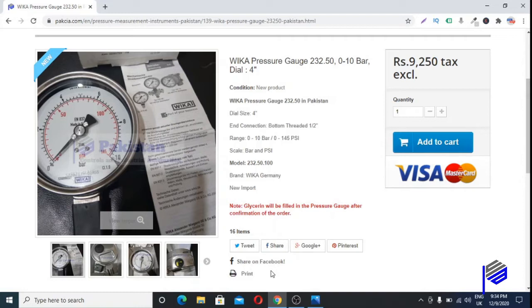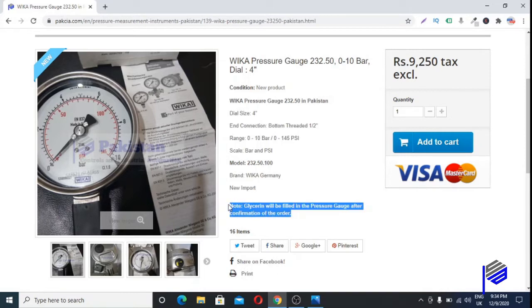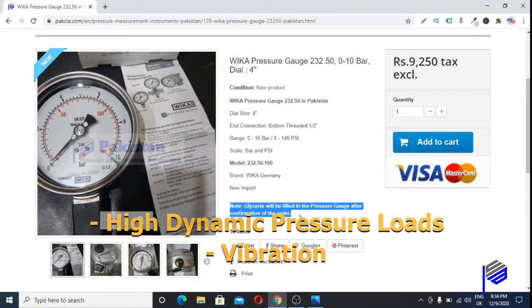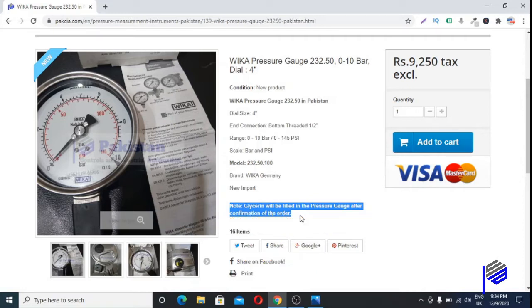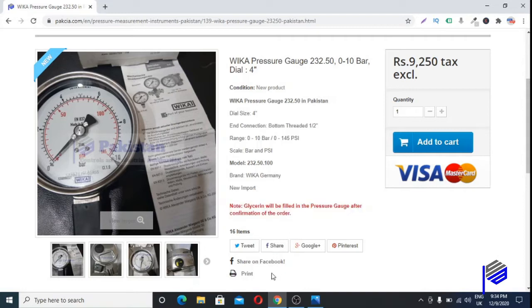You may have a question in your mind: why do we need to use glycerine fill in a pressure gauge? Glycerine-filled gauges are used in special applications where there are high dynamic pressure loads and vibrations are involved. For normal applications, we can use pressure gauges without glycerine fill.